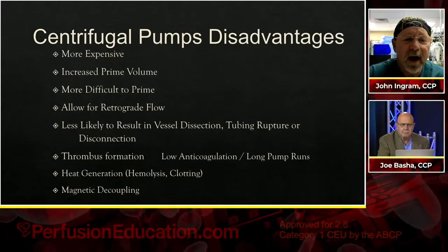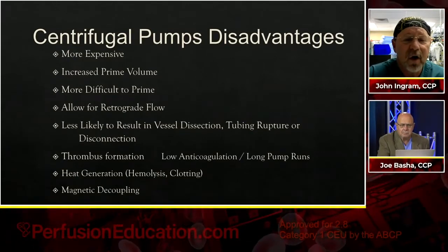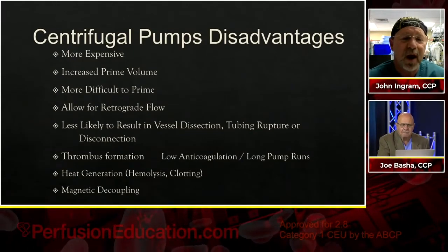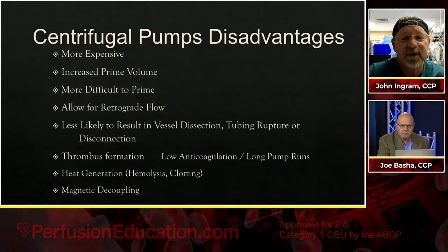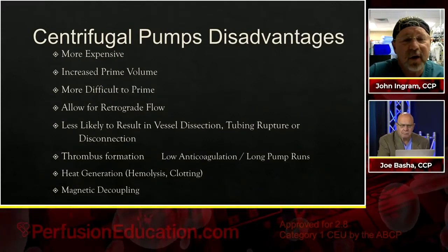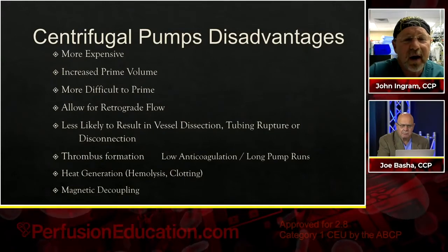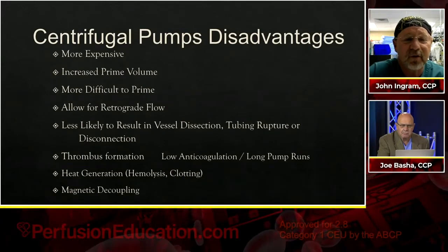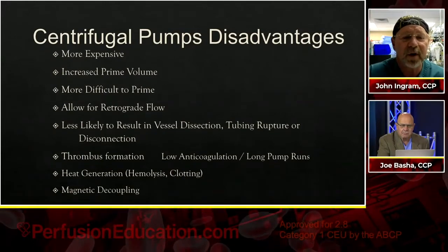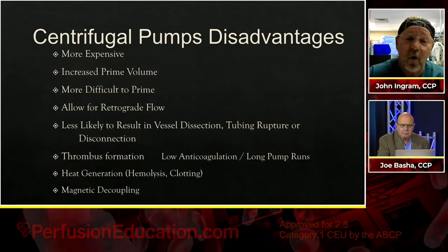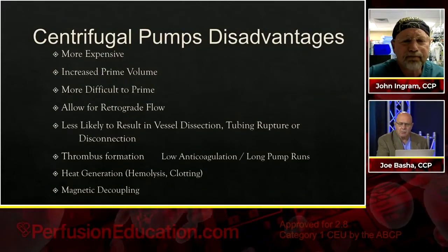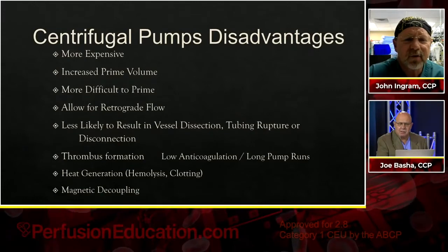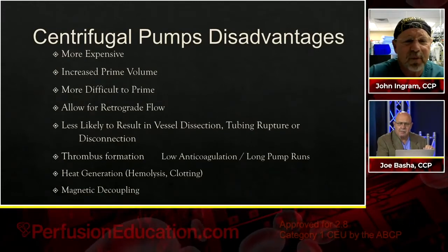And you can have retrograde flow occur with a centrifugal pump. Remember, it's relying on the amount of RPMs that you're telling it to run at to continually push in a positive direction. If you decrease those RPMs, you can either have zero flow or even a negative flow. But it's far less likely to result in vessel dissection, tubing rupture, disconnection.